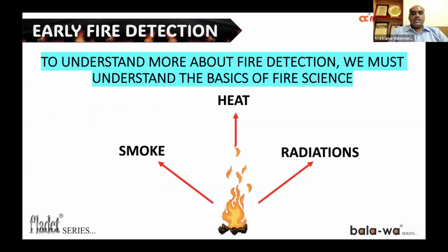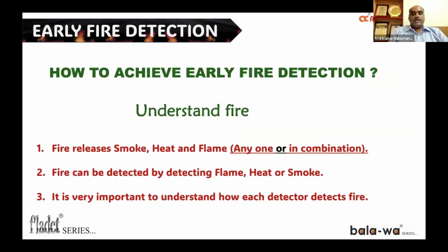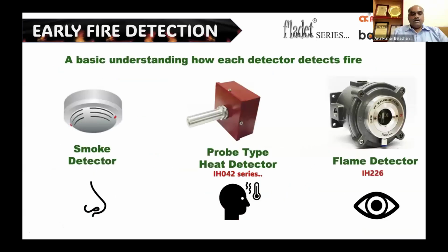In order to detect fire, we need to understand the basics of fire. Fire, being an exothermic reaction, gives out smoke, heat, and light radiation. Light radiation means flame, ember, or spark. So to detect a fire, it is very easy: we need to detect any one of, or a combination of, these parameters, that is smoke, heat, or light radiation like flame or ember. A simple way to understand is by equating smoke detectors to our nose, heat detectors to our skin, and flame detectors to our eye.